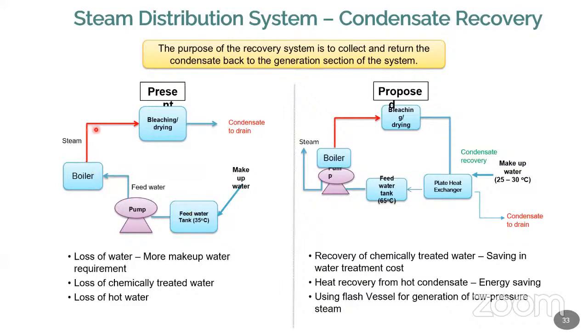Now the steam can flow to the application. After the application, the steam starts to condense. And the condensate water, I didn't use it, right? I didn't use it. Rather, if I use the condensate water with the help of a heat exchanger, I can take the water.